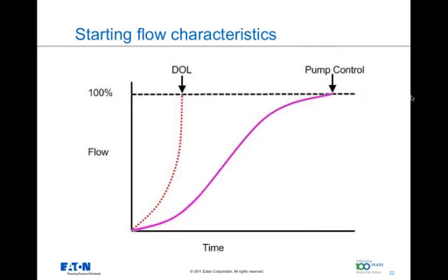Now, how can a soft starter help in such situations? Soft starters come with a special pump algorithm which minimizes and in many cases eliminates the water hammer effect. This chart shows the difference in flow characteristics between across the line and pump control. As you can see, direct online, which is DOL, can quite rapidly increase the flow rate. DOL is, in other words, an across the line starting mechanism. Pump control, which is available in a soft starter, follows a smooth S-curve for an extended time. This reduces sudden change in flow by controlling the acceleration torque of the pump motor and extending the time to produce 100% flow. There are no sudden changes in torque, and hence there is a reduction in surge. Therefore, water hammer is reduced in the pumping system.